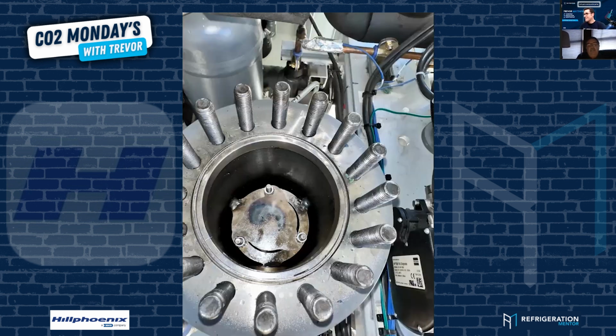Yeah, it's very important. And this is the inside of a Westermeyer. They got a strong back in there. I recommend loosening those 3 nuts. They're hex nuts with stars on the bottom with a built-in washer. The Westermeyer recommends changing them. I say leave them in place, because if you drop that nut, you're going to go fishing for it. Then you turn that to the right and pull the separator filter out. Hopefully it comes out easy and the bottom gasket comes with it. Yep, exactly. It shouldn't take more than 45 minutes to do this.